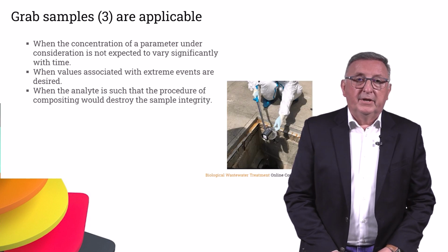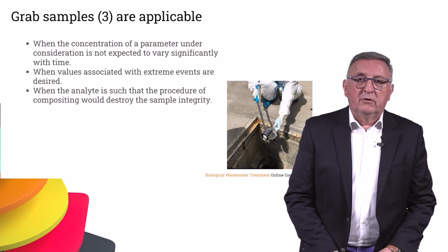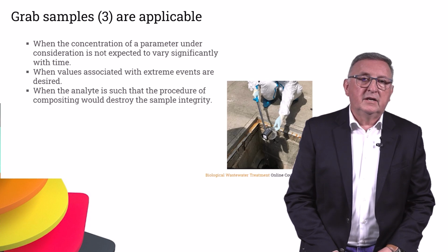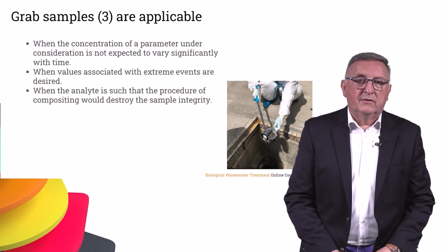Grab samples are applicable when the concentration of a parameter under consideration is not expected to vary significantly with time, when values associated with extreme events are desired, or when the analyte is such that the procedure of compositing would destroy the sample integrity.